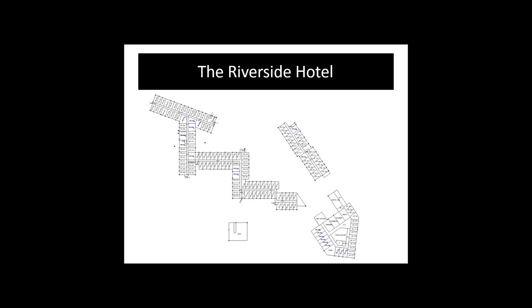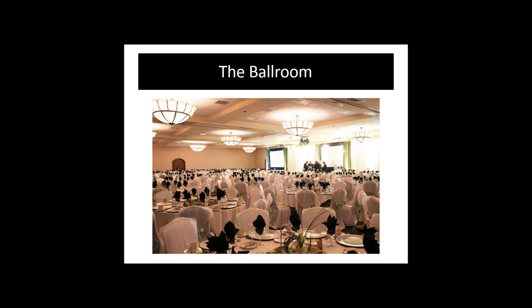I'm not going to say which one of the integrated design lab staff told me this, but they said that the building vents were designed by an architect and not by an engineer because they were the right size for the hole that was there, not the right amount of air that needed to go out of the building. Sorry for that. But really, that was probably one of our biggest gains right off the bat. We found out we were probably exhausting twice as much air, and we've just got gravity dampers in there. So as you raise your static pressure, it automatically exhausts more air. We went through and plugged half the holes around the building, and it was amazing right off the bat.